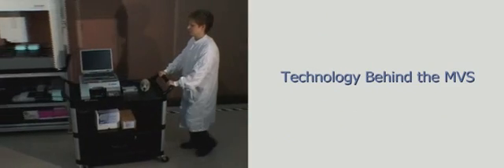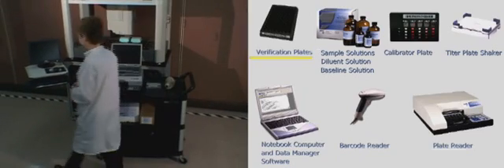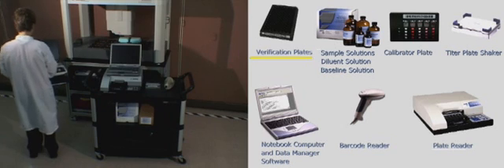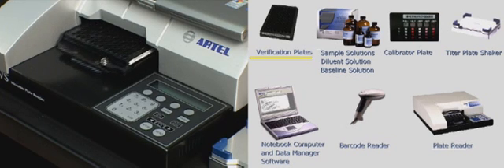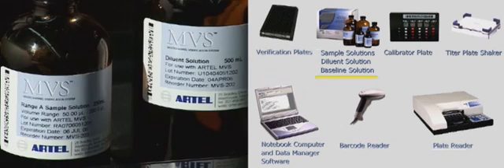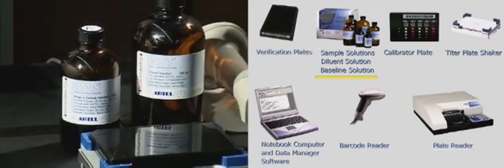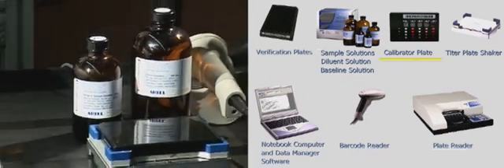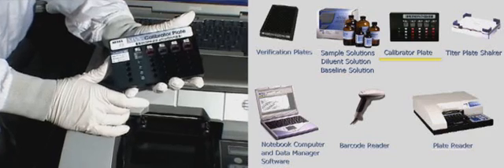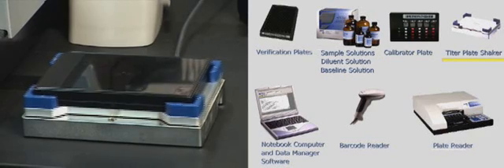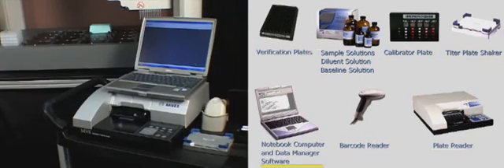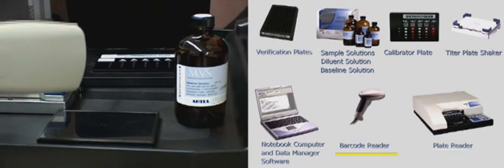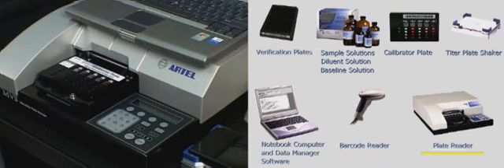Now we will review the technology behind the MVS. The MVS is a complete mobile system composed of the following parts: characterized verification plates, sample solutions, diluent solution, baseline solution, the NIST traceable calibrator plate, the titer plate shaker, a notebook computer equipped with data manager software, a barcode reader, and the plate reader.